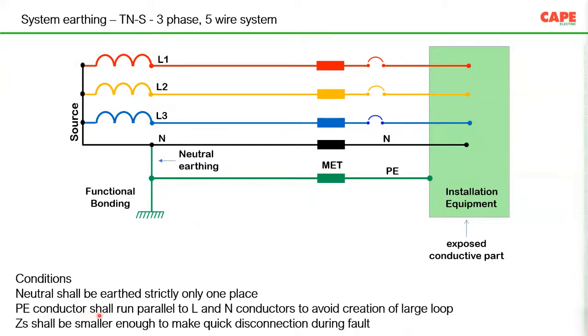The protective earth conductor, the fifth wire, shall run parallel to the line and the neutral conductor to avoid large loops. The fault loop impedance of each and every final distribution circuit must be such that the protective device is able to disconnect the supply. So it is not only a TN-S system. People think that if you make 5 wires, you have a TN-S system. No, it is not like that. A TN-S system means all the conditions of TN-S must be followed.